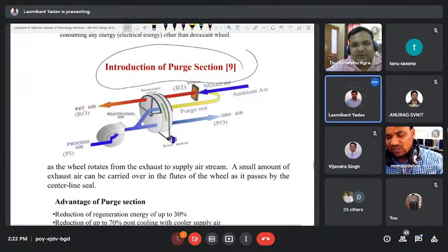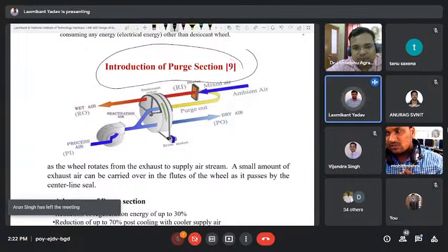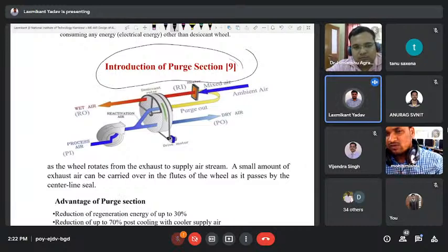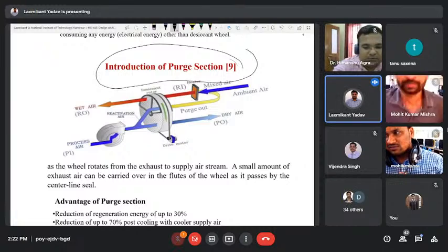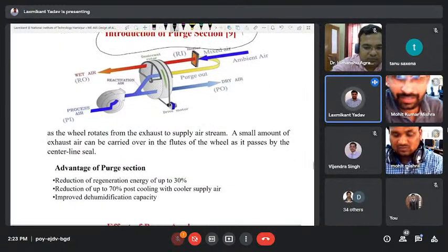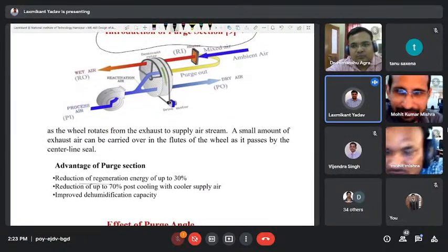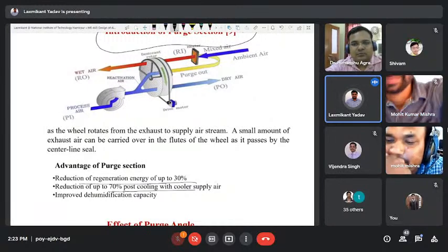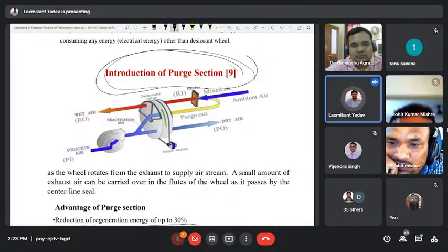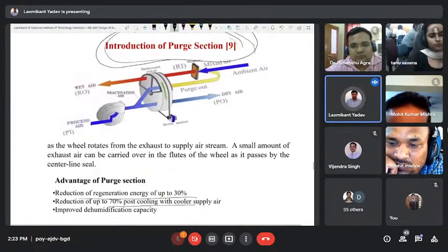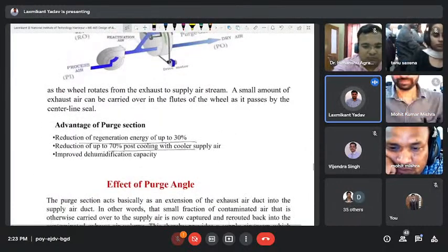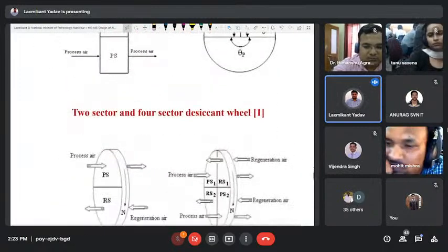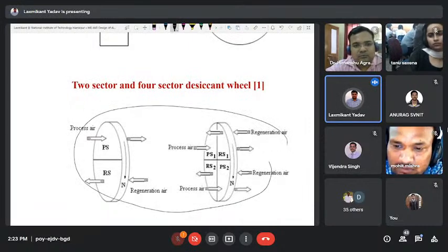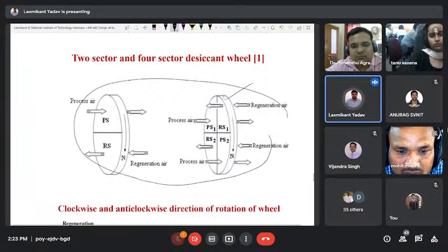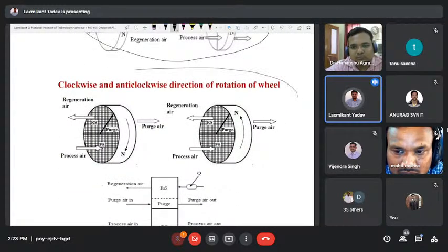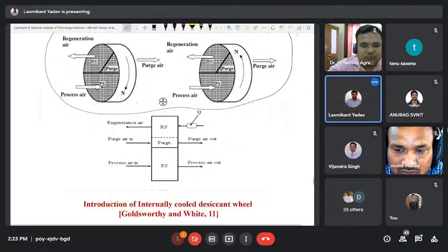Okay, thank you. So these are the purge sections. We can install the purge section, a third section. Generally the desiccant wheel is divided into two sections, so we can install the purge section, and that purge section will reduce the power consumption also. Okay, so the reduction of regeneration energy is up to 30%, and up to 70% in post cooling. So we can all do research in the purge section. We can divide the desiccant wheel into many sectors and introduce the purge section. So this is the scope of research. The effect of purge angle can be studied, and similarly we can divide the desiccant wheel into more sectors, such as 4 sectors. So these are new configurations of the wheel.